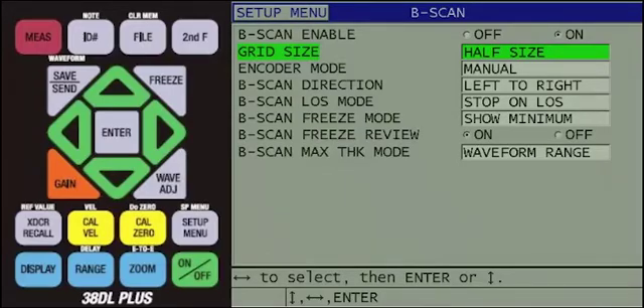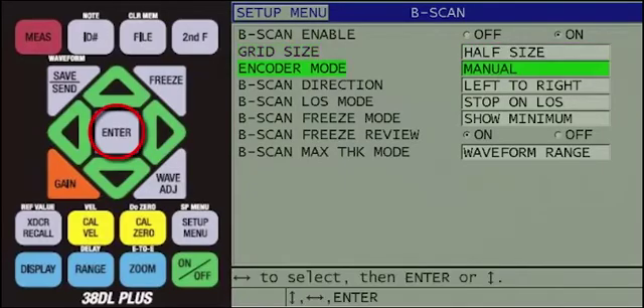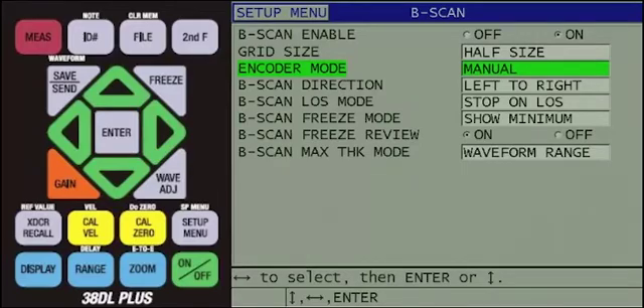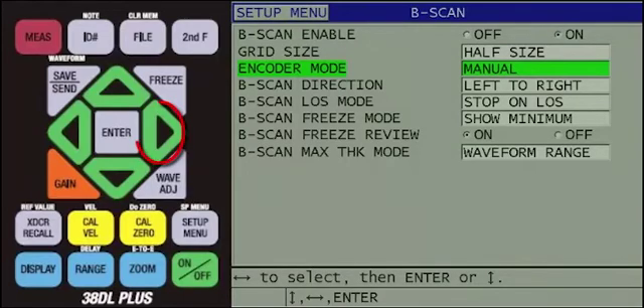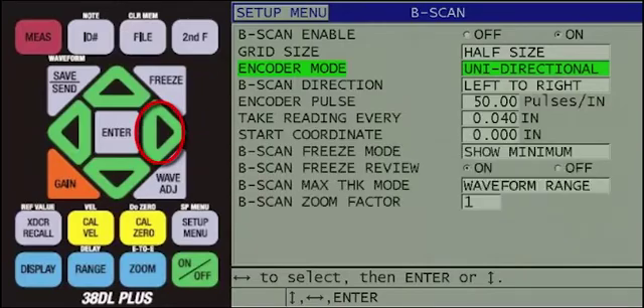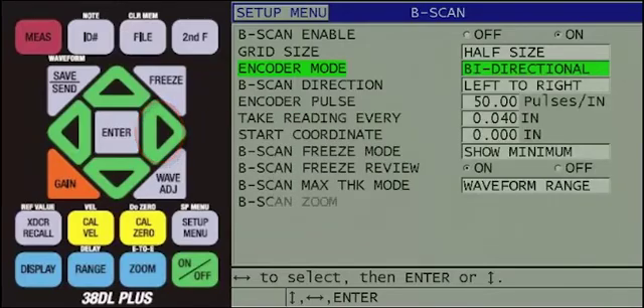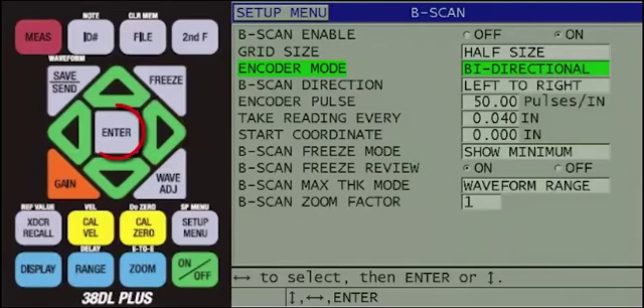Continue pressing the Enter key until you get to encoder mode. For encoded B-Scan, the encoder mode can be set to either unidirectional or bidirectional as discussed in previous slides. Generally, bidirectional is used since it allows the user to back up the buggy to fill in areas of LOS if needed. Press the right arrow until the encoder mode is set to bidirectional, then press the Enter key twice.